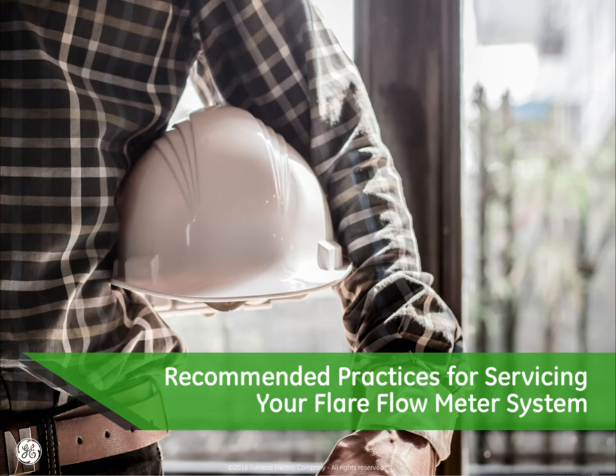For my portion, I plan to discuss the importance of proper flare servicing on any flare flow meter. As Randy and Dan have both highlighted, these meters play a critical role within a variety of industries, and because of that, ongoing service is going to be key to ensuring that you're receiving the best out of your product. As you evaluate any future meter purchases, I suggest that you not only consider product specifications, but also servicing capabilities. Flare flow meter OEMs are not only responsible for producing professional measurement devices, they must also provide quality technical support and the field service expertise necessary to prevent operational issues and quickly resolve any problems that may arise.